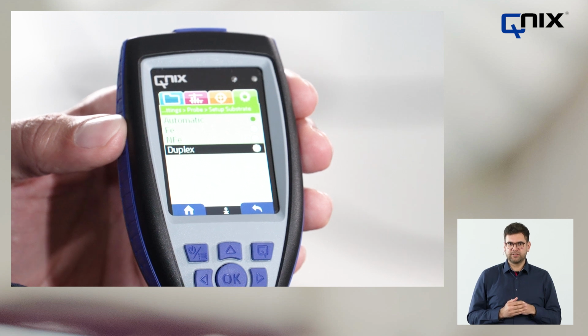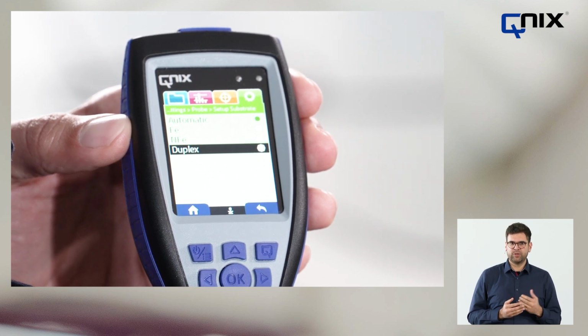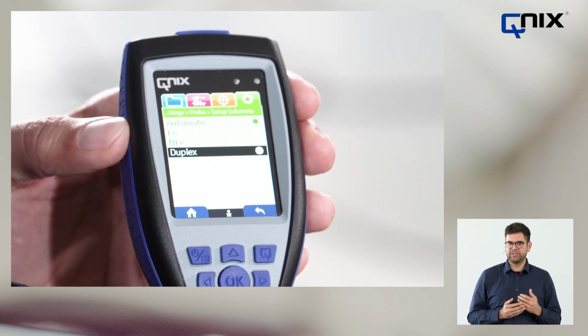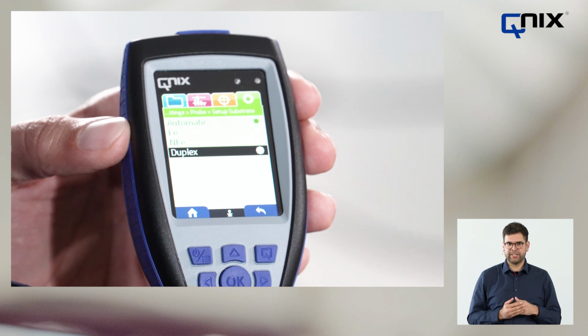Last but not least, the duplex mode. In this mode, the device offers the possibility to measure several protective layers on a ferromagnetic substrate. This is the case, for example, when a metallic, non-ferromagnetic protective layer, such as tin or zinc, has been applied on a ferromagnetic substrate such as steel. And this protective layer coated with a non-conductive coating.